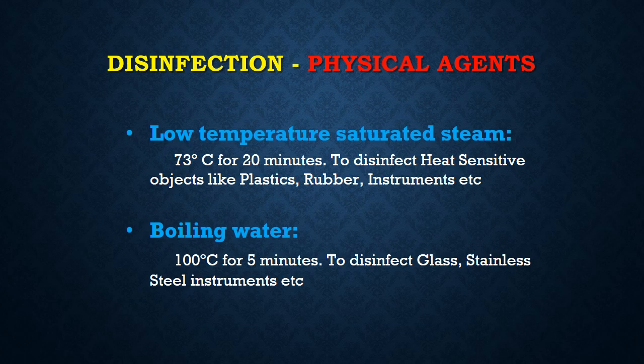Physical agents that can be used for disinfection are low temperature saturated steam. So at 73 degrees centigrade for 20 minutes, heat sensitive objects like plastics, rubbers, and other instruments can be placed.